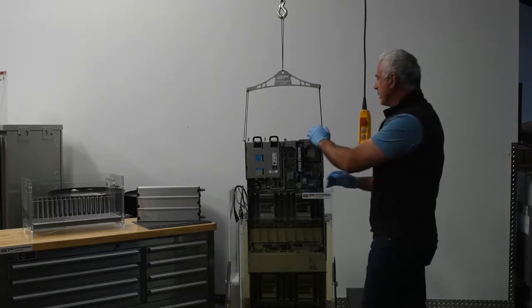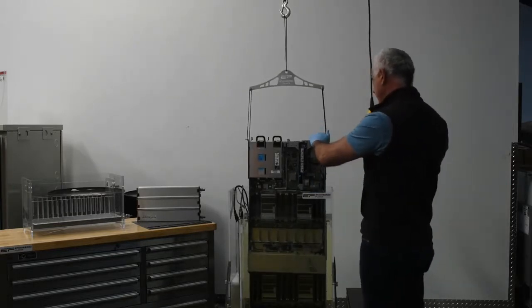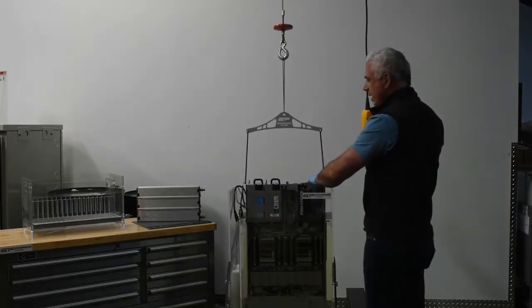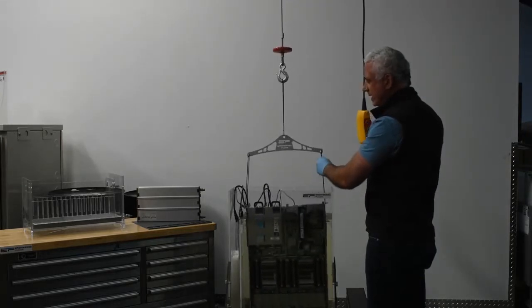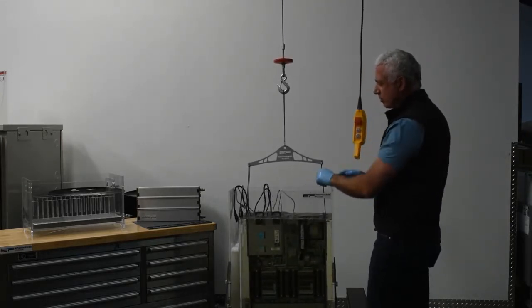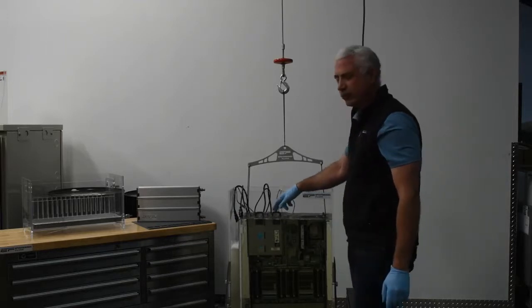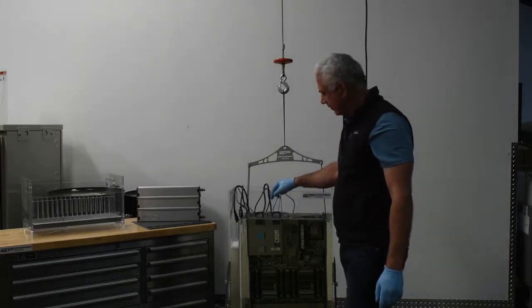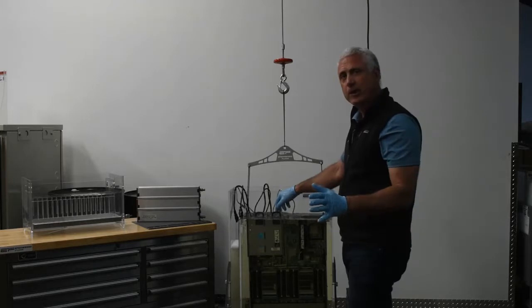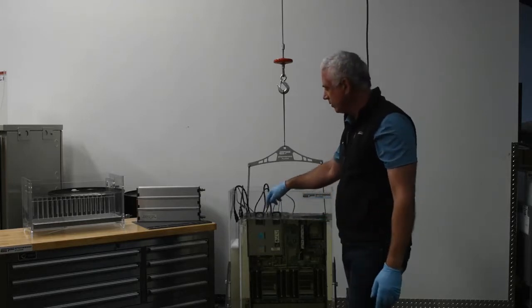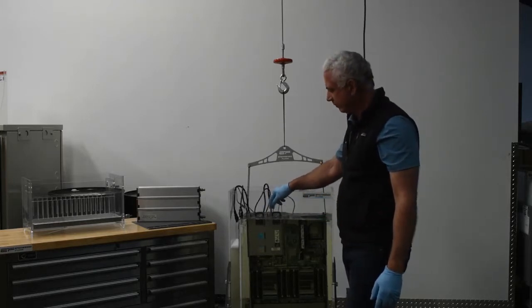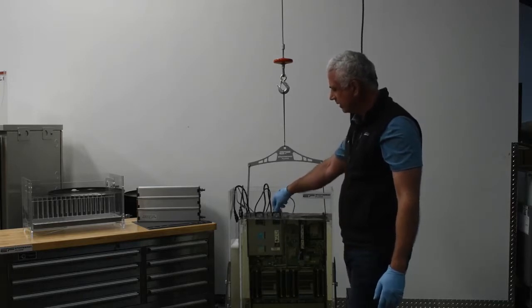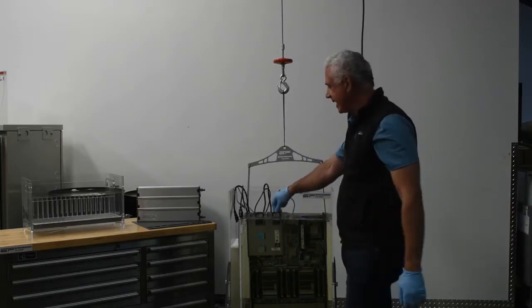So now I'm going to bring this server down and this next part is very important. You want to make sure before reconnecting the power on the server that you want to make sure that these fans are under the surface of the fluid. If you do not do that they'll spray fluid and coolant everywhere and you want to make sure that that doesn't happen. You spend a lot of money on your coolant and we want to make sure that we keep it in the tank.